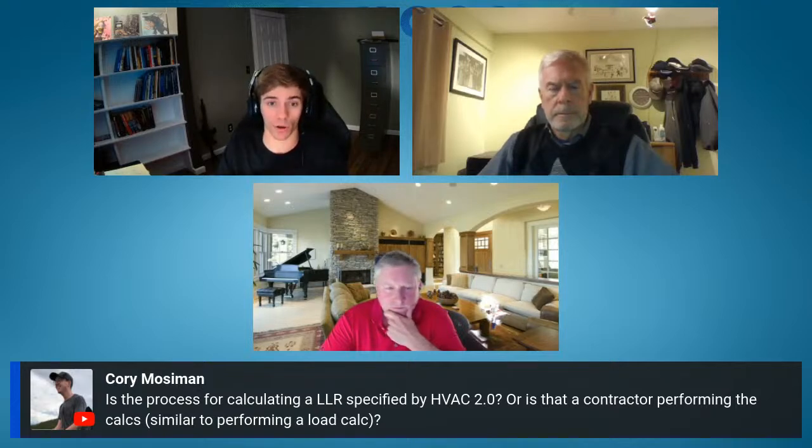It is better for it to be fairly wide. You don't want a likely load range of somewhere between 2 and 2.5 tons, unless you are testing some things. In my opinion, to be accurate enough to get the likely load range within half a ton, you should be doing a lot of other things. And if you're doing those other things, you should be doing paid consulting, not a free quote. So it's drawing that line of where to go.